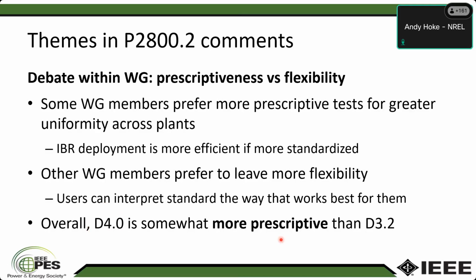And it's still a recommended practice, right? It's saying here's a recommendation on how to check conformity of the plant, not here's the way you have to do it. Of course, we all know sometimes some user of the standard might pick up a certain piece of it and say, we're doing it this way, and now you have to do it that way because the authority governing the interconnection requirements said so. Anyway, that's one theme, is this slightly more tilt towards prescriptiveness, but still pretty general in 2800.2 draft 4.